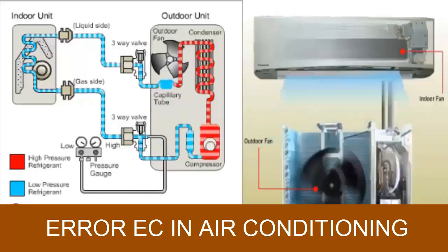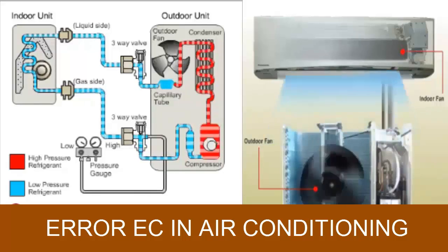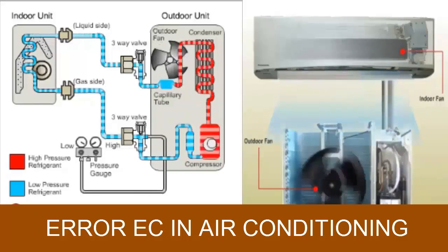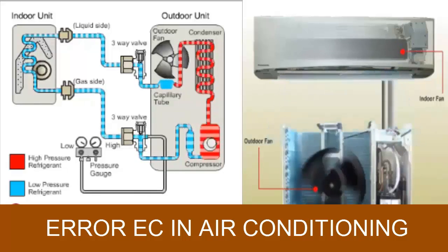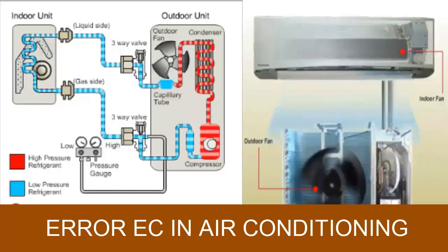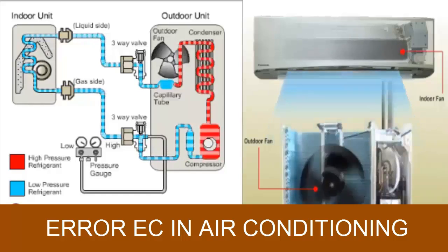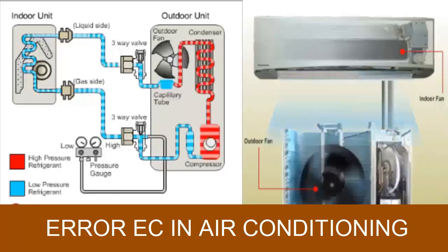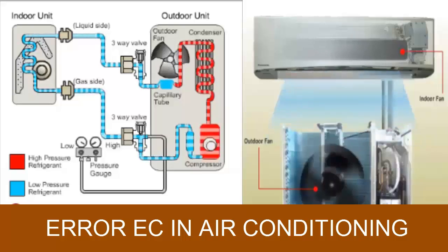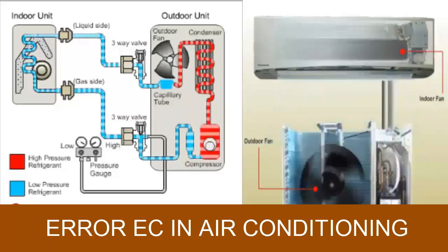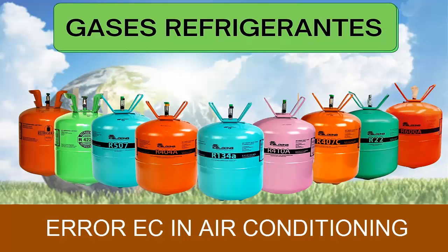Today we present: what does the error EC mean in air conditioning, and what should be done to correct it? The EC error code stands for refrigerant error and indicates that there is likely a refrigerant gas leak in the air conditioning unit.